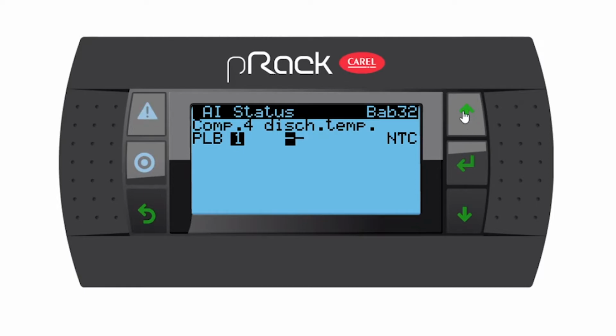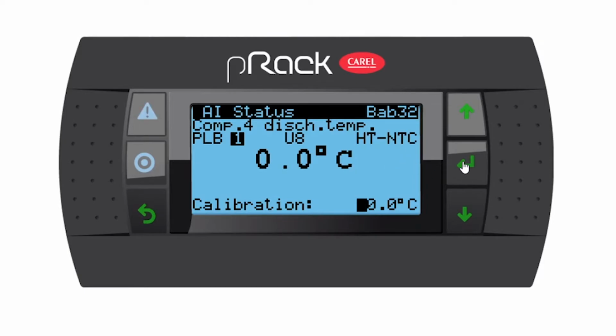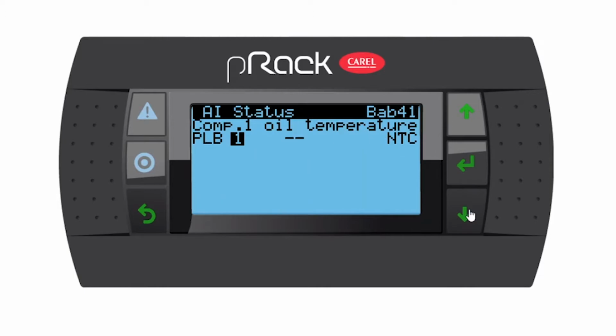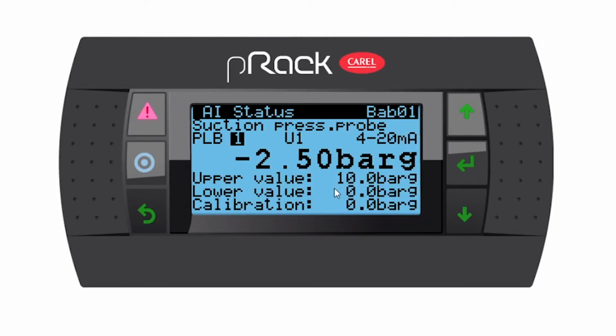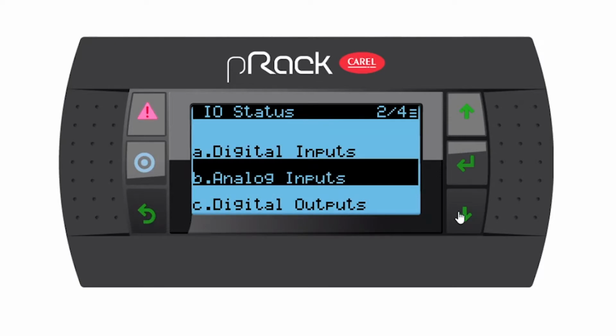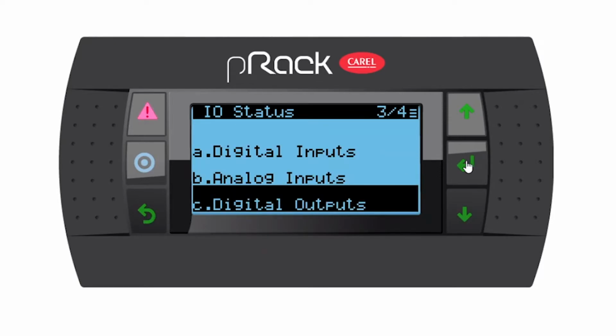And then the last compressor, U8. HTNTC. Perfect. 0 calibration. Let's go down. Do you have a compressor 1 oil temperature? No, we don't, so we skip it. Compressor 2 oil? No. Compressor 3 oil? No. Compressor 4 oil? No. And then we're back at the beginning. So perfect. Now we've assigned all the analog inputs. So I'm going to escape from this menu and go to digital outputs.